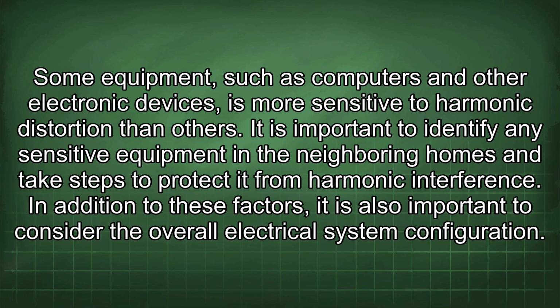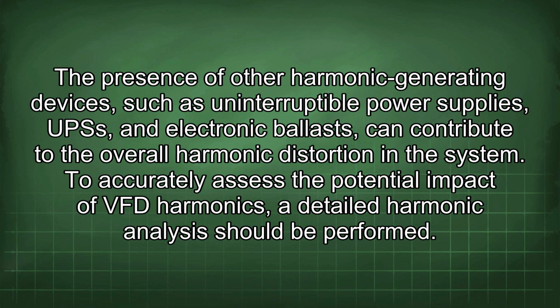In addition to these factors, it is also important to consider the overall electrical system configuration. The presence of other harmonic generating devices, such as uninterruptible power supplies (UPSs) and electronic ballasts, can contribute to the overall harmonic distortion in the system. To accurately assess the potential impact of VFD harmonics, a detailed harmonic analysis should be performed.